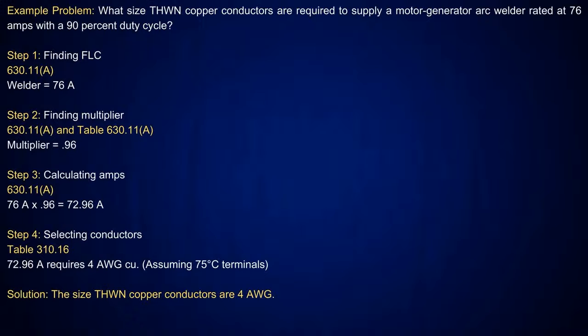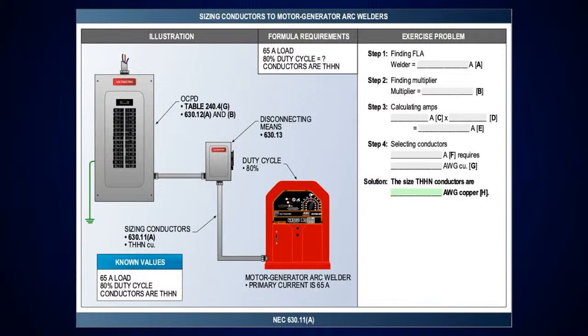Guess what? I have a note there. That's something I need to consider after I do this calculation. It's in a temperature here. I need to consider this. All right, so we had a .96 multiplier. Take that times 76, gives me 72.96. The next size above that is 85 amps in the 75-degree C column, which will be a number 4 conductor. Okay, and there you go.